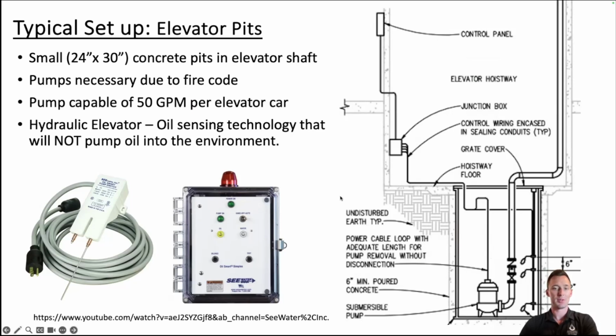So 99% of what we sell nowadays is an oil smart control panel. And we'll look at how it's set up. I even have a video for you guys, but we've done away with floats and we have this deck of cards looking item that gets attached to the discharge pipe. And it sees that once water submerges both probes here, the pump turns on, but it won't turn on if the oil touches these probes. So you have a layer of oil on top of the water that continues to remain within the pit and never gets pumped out. So we'll look at that in a second.